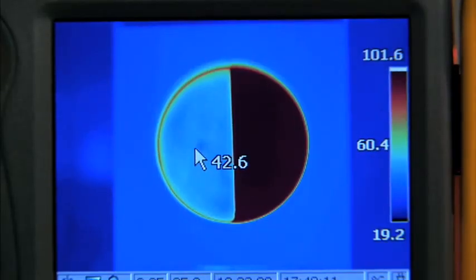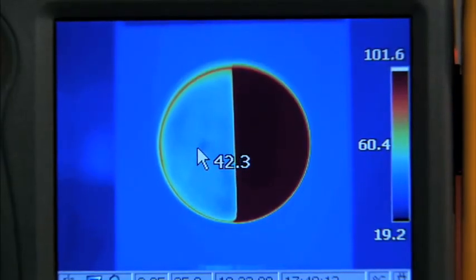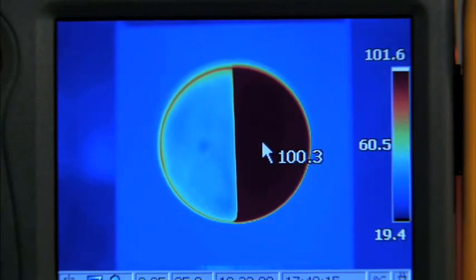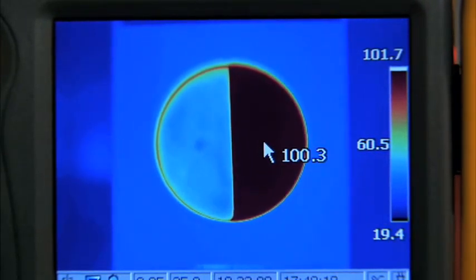Now, what does this mean in terms of calibration? What it means is that we need to know the emissivity and be able to match the surface's emissivity with our IR thermometer.